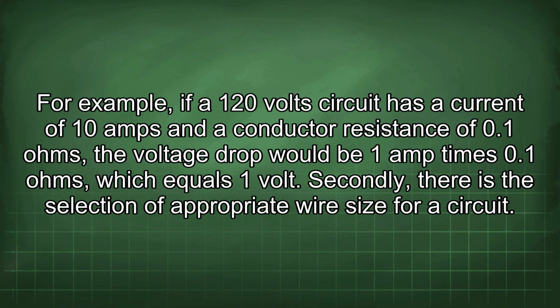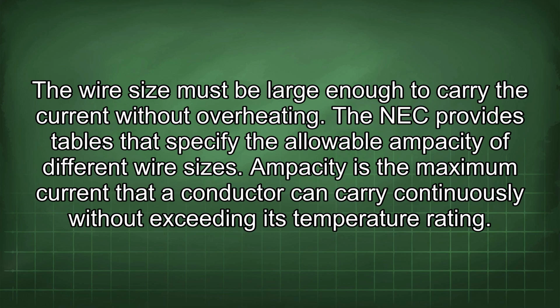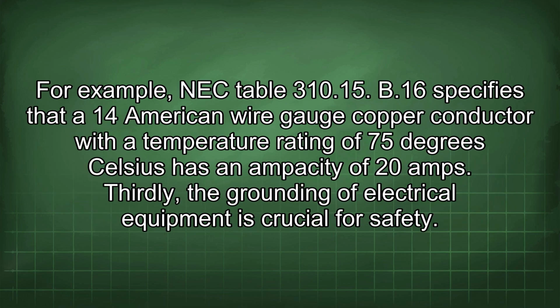Secondly, there is the selection of appropriate wire size for a circuit. The wire size must be large enough to carry the current without overheating. The NEC provides tables that specify the allowable ampacity of different wire sizes. Ampacity is the maximum current that a conductor can carry continuously without exceeding its temperature rating. For example, NEC table 310.15.B16 specifies that a 14 American wire gauge copper conductor with a temperature rating of 75 degrees Celsius has an ampacity of 20 amps.